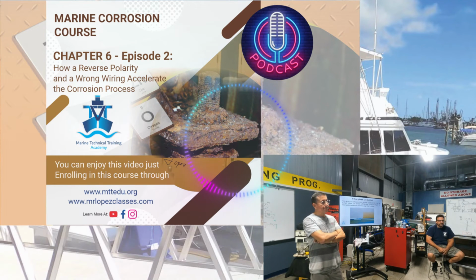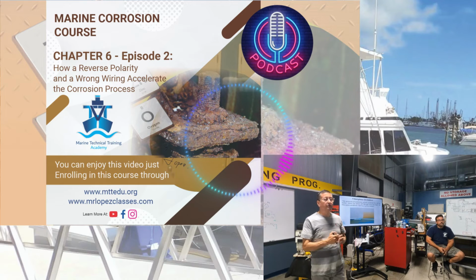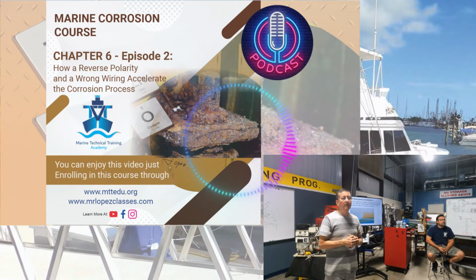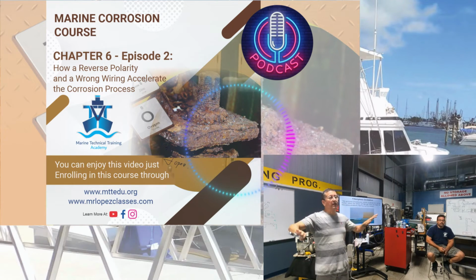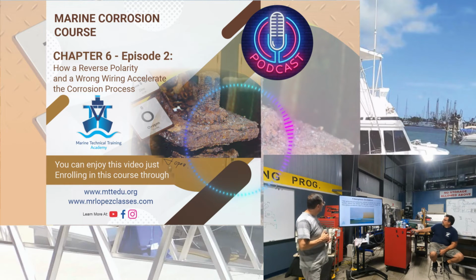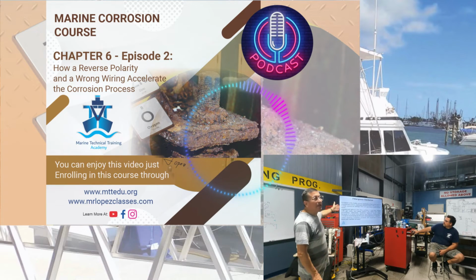Simple. For the voltmeter, one hotline is connected here to the hotline bus bar, and the neutral is connected to the neutral bus bar. And the frequency meter is connected neutral with neutral and hot with hot. That's too simple. Connect the voltmeter, frequency meter, and ammeter. The ammeter should be with the donut, and the donut should be connected through the hotline cable.